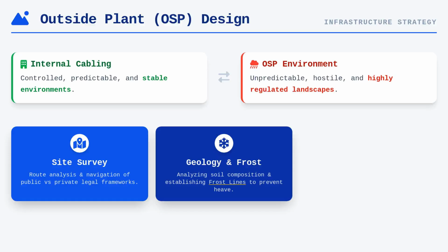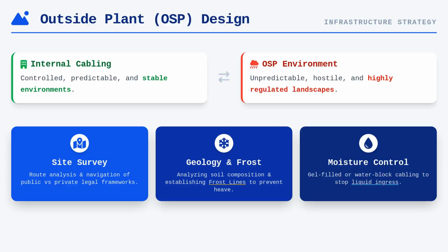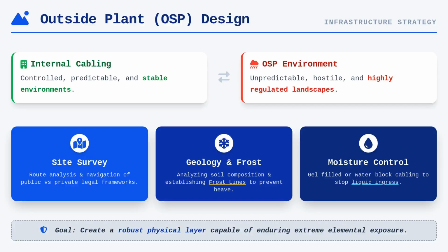Your role as a designer starts long before a shovel hits the ground, specifically with a comprehensive site survey and route analysis. You must account for soil composition, which significantly impacts the difficulty of excavation, and establish the local frost line to ensure all subterranean infrastructure is placed at a depth that prevents frost heave from damaging the conduits. Furthermore, the water table level can influence the choice of materials, as high moisture content in the soil often necessitates the use of gel-filled or water-block cabling to prevent liquid ingress. By mastering these environmental variables, you create a robust physical layer that can withstand years of exposure to elements that interior systems never encounter.